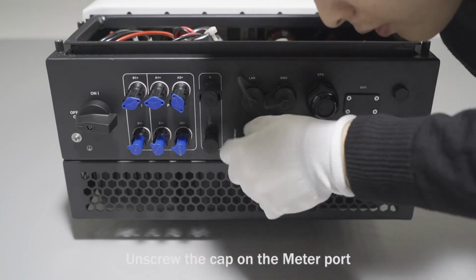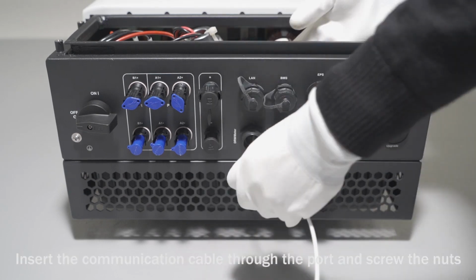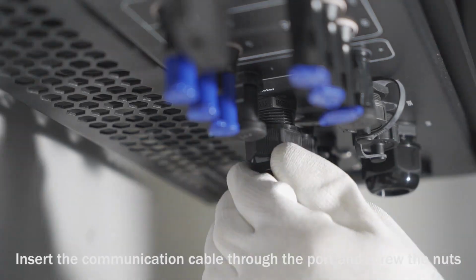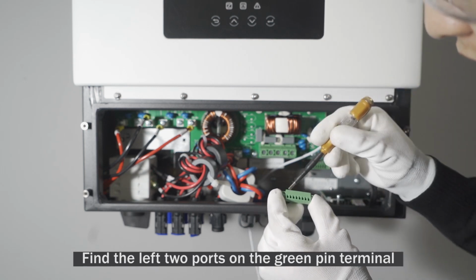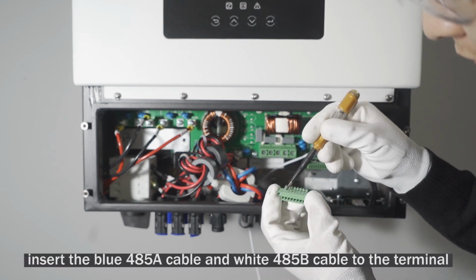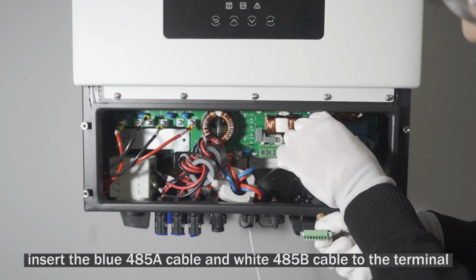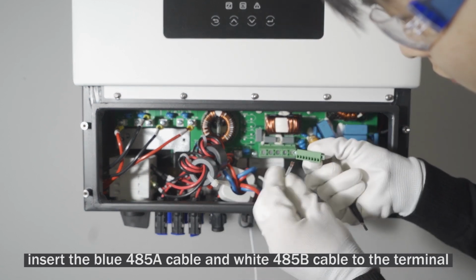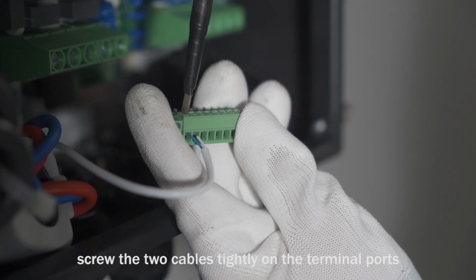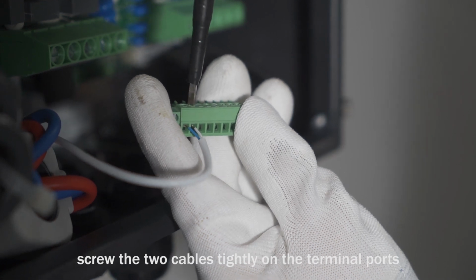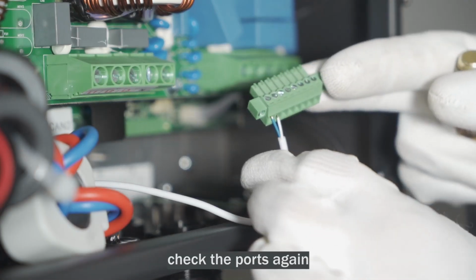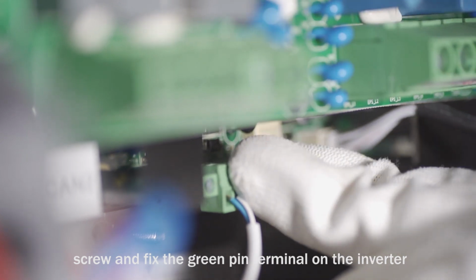Unscrew the cap on the meter port. Insert the communication cable through the port and screw the nuts. Find the left 2 ports on the green pin terminal. Insert the blue 485A cable and white 485B cable to the terminal. Screw the 2 cables tightly on the terminal ports. Check the ports again. Screw and fix the green pin terminal on the inverter.